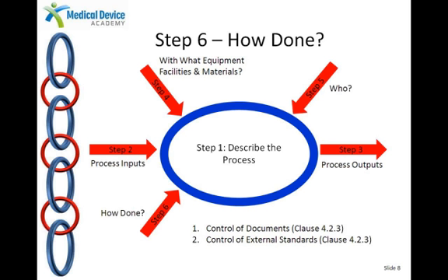But the reason why I often ask this last, if not at all, is because it takes a lot of time to read a procedure. Part of the beauty of this method is that I don't have to read a procedure and write a checklist. Instead, I have to learn this 7-step process and ask questions and take notes. It's always the same. It's really simple. So what I do is I'll say, I know for the calibration of the calipers that they're using, what happens if they drop it on the ground?